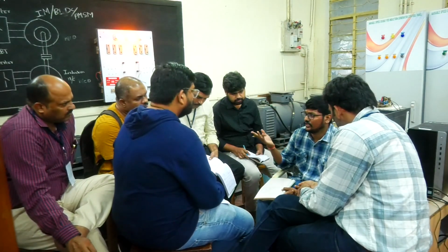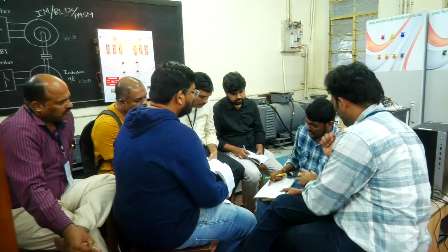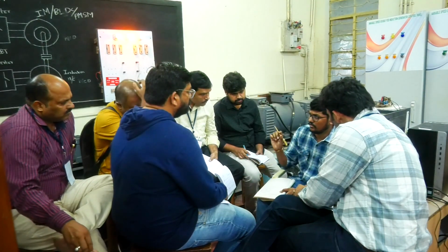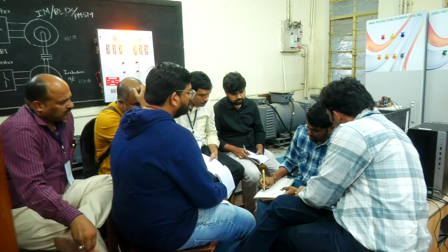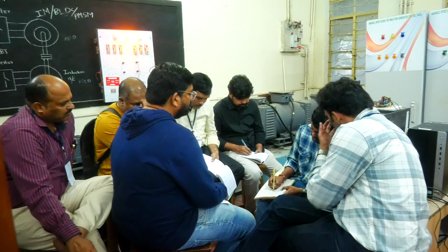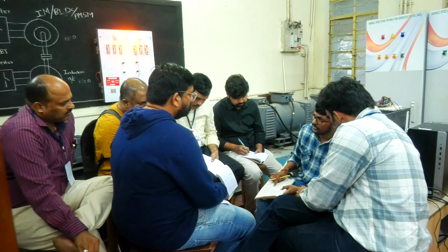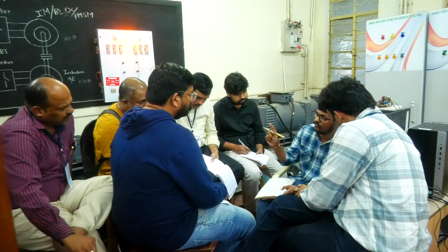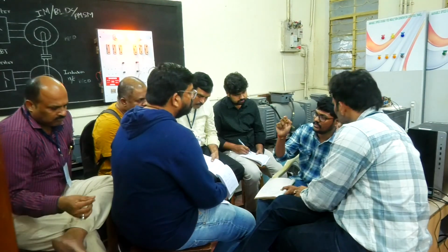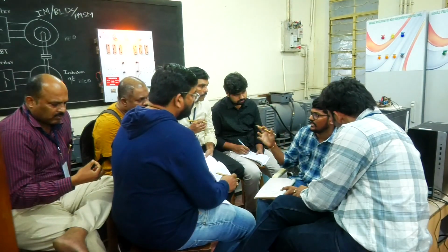3000 pulses per one revolution also. According to the number of pulses per revolution, this particular signal will change for the incremental input. According to that, our control logic will also vary, our scaling will also vary. So for 1024 pulses, that means for every revolution it will produce 1024 pulses. Inside there is a disk with a hole-type arrangement where they send some light signal, and based on how many times it is hitting, they calculate the number.